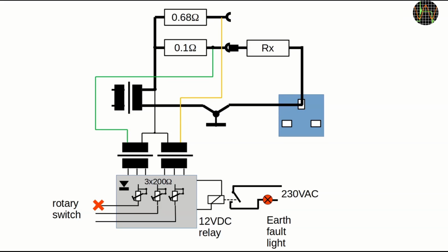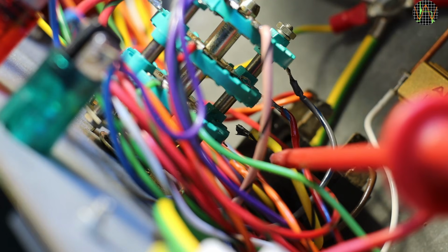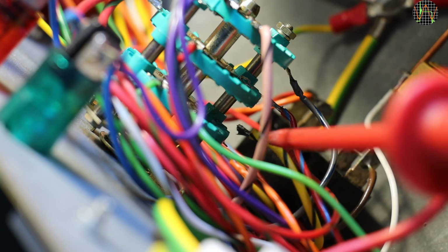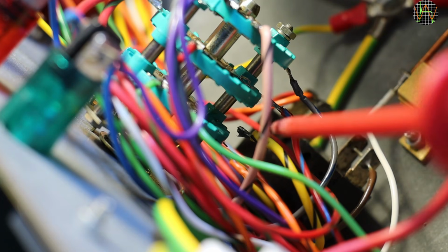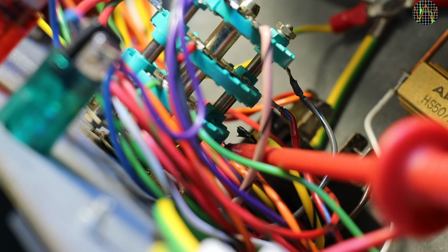As you have seen, the fault light in the normal setting is always on, even though the resistance is well within the green area. Further, the trim pot for this range doesn't do anything. It turns out both are symptoms of the same fault. This trim pot has lost its connection to the rotary switch and its lower leg is just floating. Because of that, it has no effect, and even the 0.05 ohm resistance is generating enough voltage to operate the relay. After carefully studying the rotary switch, I found that the yellow-black wire has indeed come loose. It's kind of tricky to see.